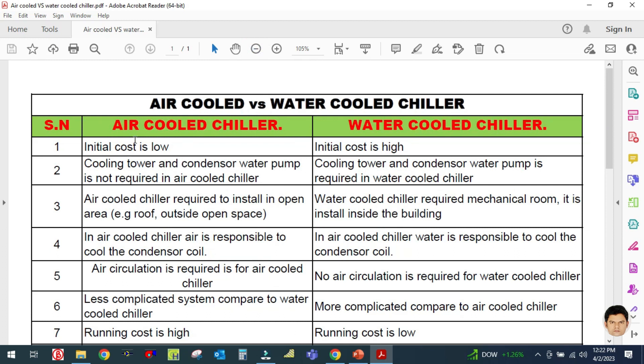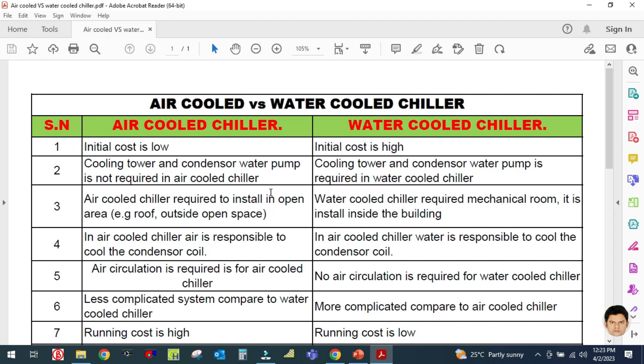The second difference is that a cooling tower and condenser water pump are not required in an air cooled chiller. The condenser water pump circulates water between the condenser and the cooling tower. Since there is no cooling tower in an air cooled chiller, no condenser water pump is required. In a water cooled chiller, both a cooling tower and condenser water pump are required.